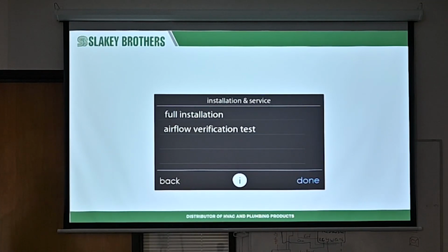Anytime you add or subtract a piece of equipment from the unit, that's Evolution, you have to do a full reinstall. So in this scenario, if you want to know airflow, you can do an airflow verification test. But in this case, if you're adding the air conditioner, or for whatever reason you put in a newer style Evolution furnace, maybe the wrong one was installed, whatever was happening, you just do a full reinstall and it does the whole commissioning process all over again. Okay?